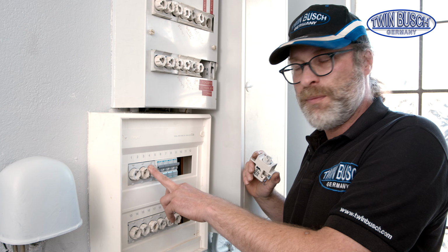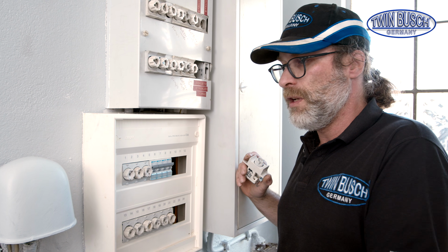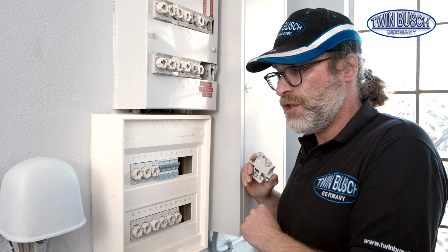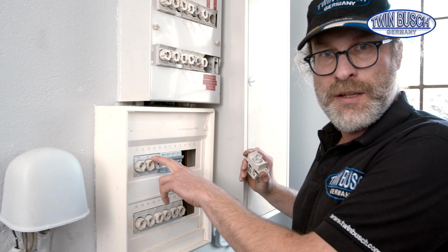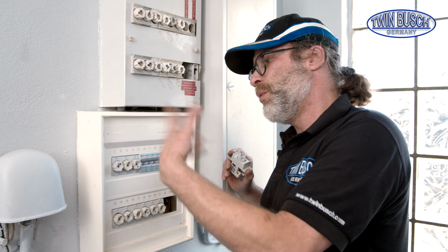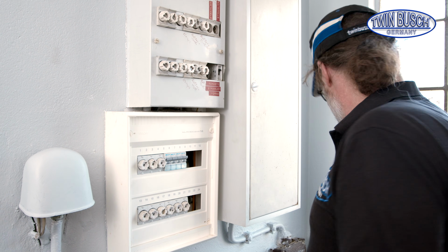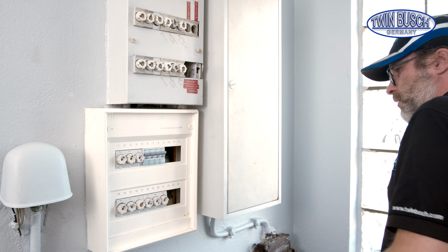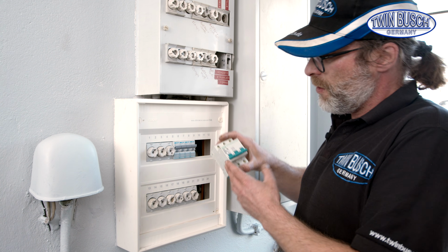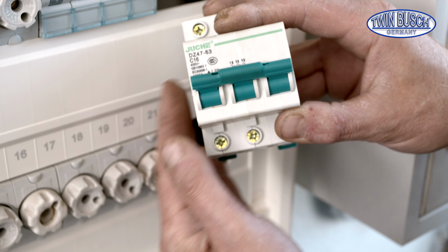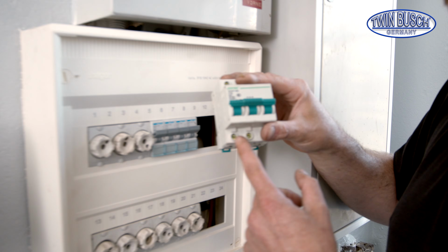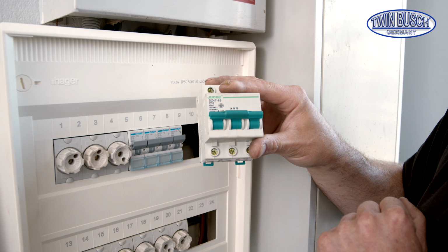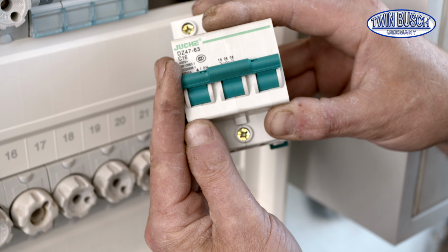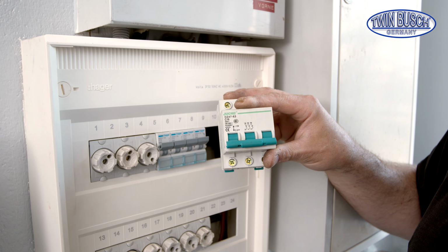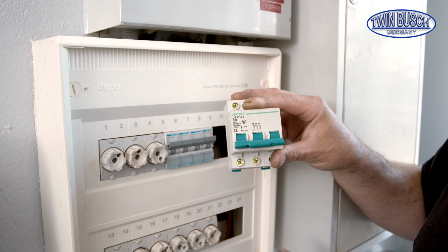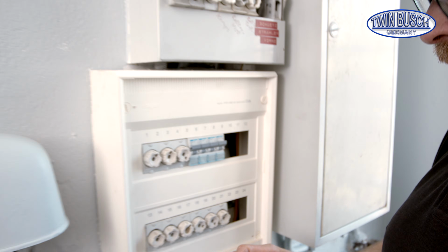Just pay attention if you have screw-in fuses. It could happen that only one fuse trips when there's any problem. Then 2 phases would still be active and the lift could be damaged because of this. Ideally, if everything is renovated, a 3-phase circuit breaker is installed. C16 400 volt model. No matter which phase has a problem where, it would trip and it would turn off the other 2 phases. This would be the ideal requirement.